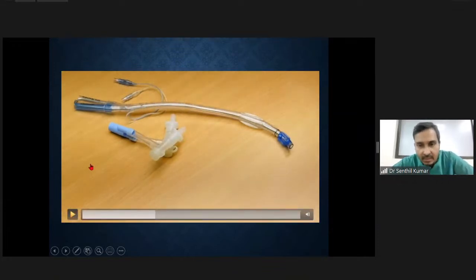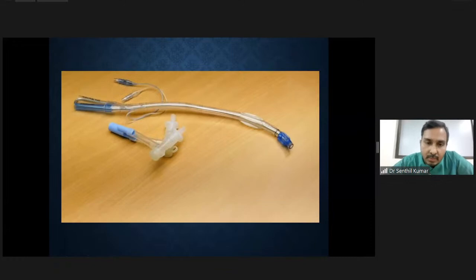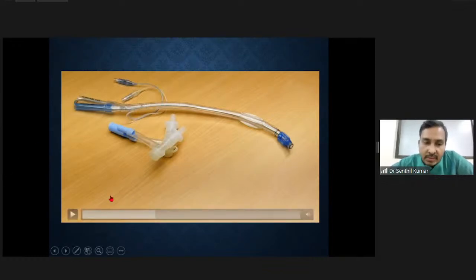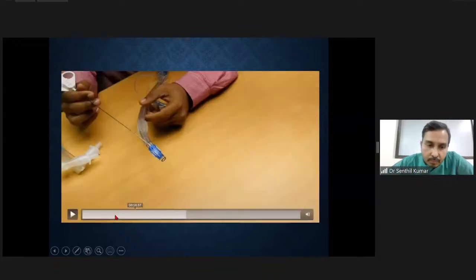Why it is designed like this is because, whenever you are intubating with the double lumen tube, even though there are conventional methods of checking, the most confirmatory method is to use a fiber optic bronchoscope and exit through the tracheal lumen while ventilating the patient through the tracheal lumen. When it exits, you are supposed to see the blue colored cuff entering the bronchus. This is the best way to confirm appropriate position of the tube. For easy identification, they have designed it as a color-coded endotracheal tube.